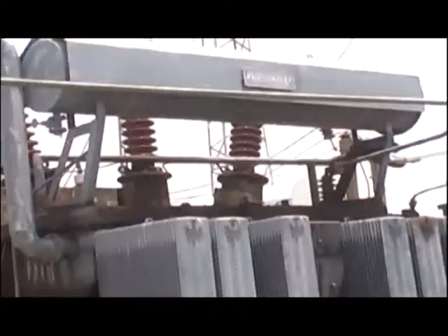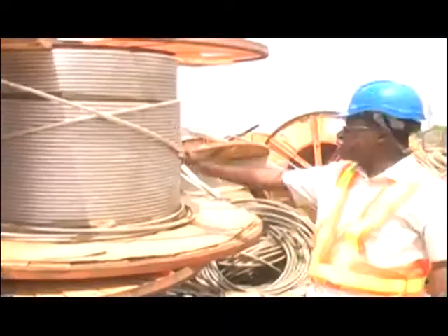To guarantee more electricity supply to Kaduna metropolis and its environs, the Transmission Company of Nigeria (TCN) is installing 2 by 60 MVA transformers, raising the Mando and Kakuri substations' capacity from 120 MVA to 240 MVA. Under the leadership of Managing Director Usman Gur Mohammed, TCN is reconducting the Mando to Kakuri transmission line to 240 MVA capacity, using aluminium conductor composite core, the best globally available.